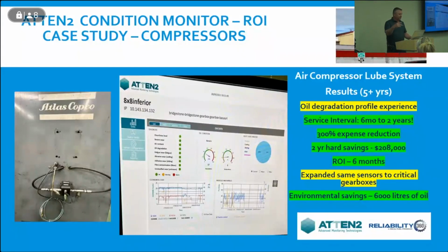Here's a screen snapshot of one example from Bridgestone in Europe, and they put it on some Atlas Copco air compressors. You'll see the sensor - in this case it was a pressurized lube oil system, and it doesn't even look like they needed pressure reducers. So they were actually able to plumb right into the existing lube oil supply lines to take their measurements.